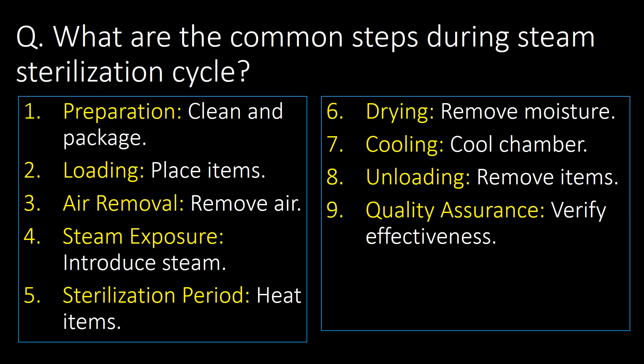What are the common steps during a steam sterilization cycle? The first step is preparation — here we clean and package the components or items. The second step is loading — as per the validated load pattern, we place the items inside the autoclave chamber. The third step is air removal — in this step, with the help of vacuum, we remove air from the autoclave chamber.